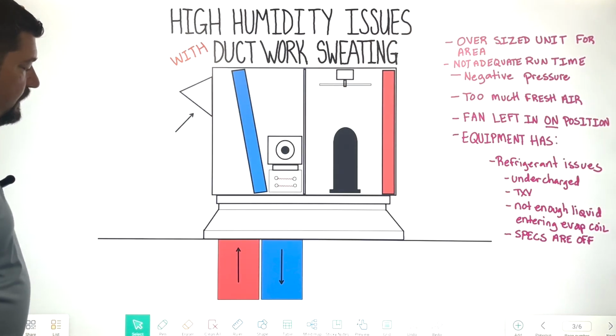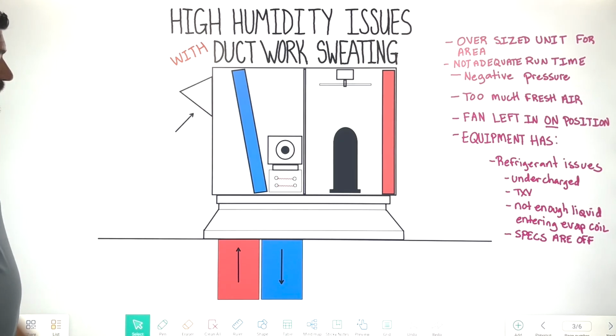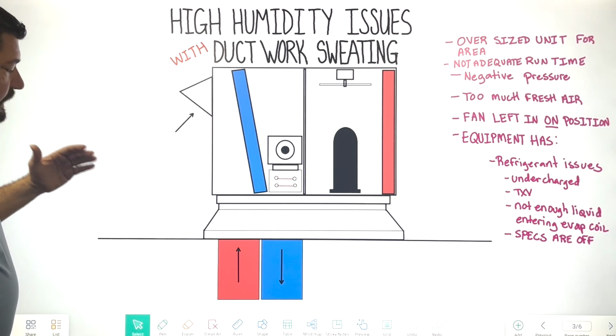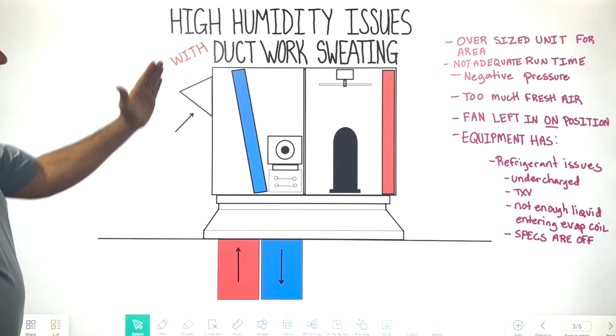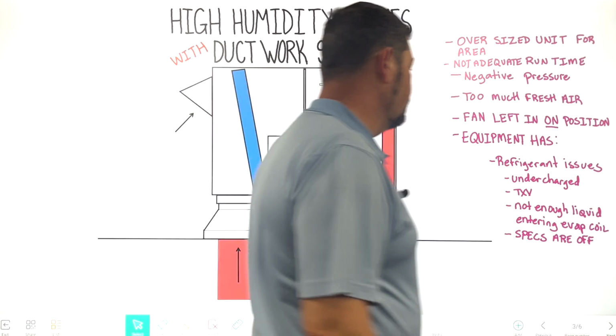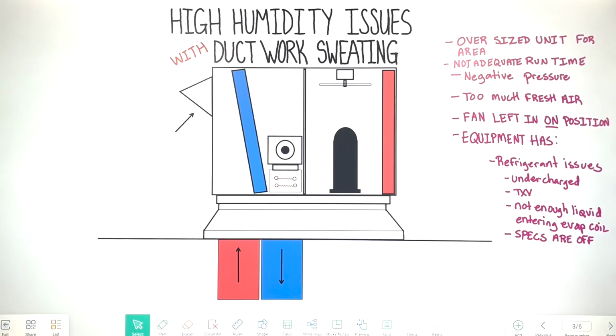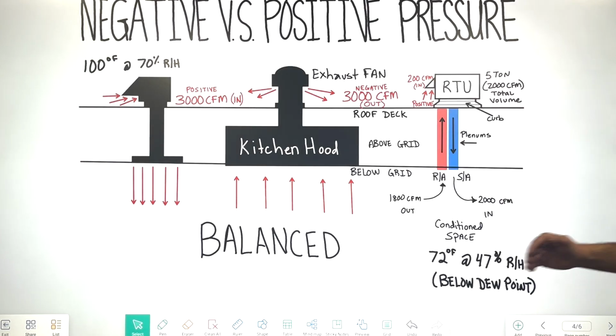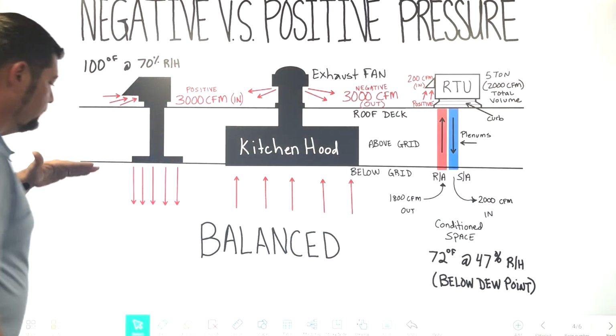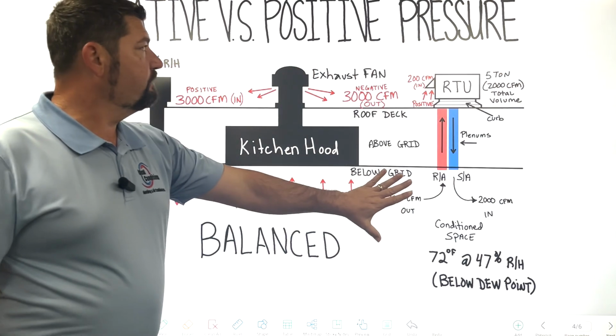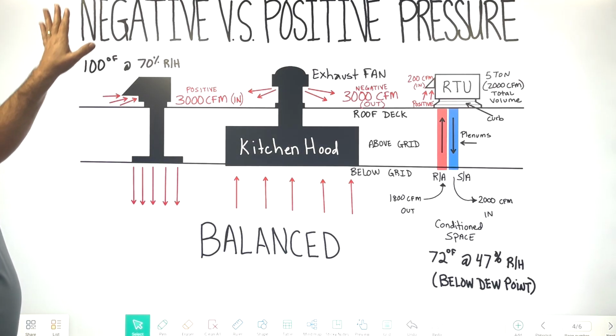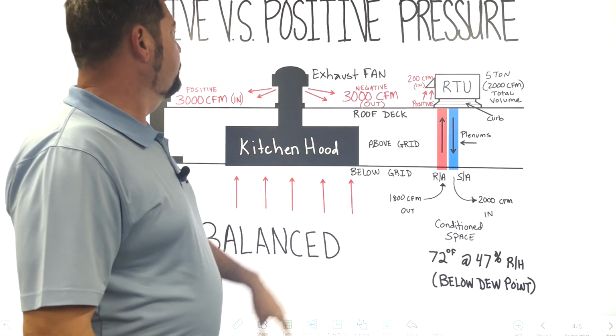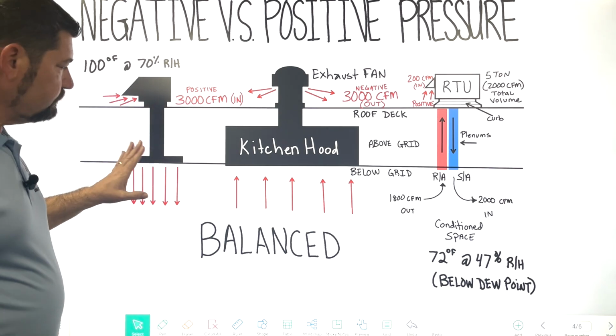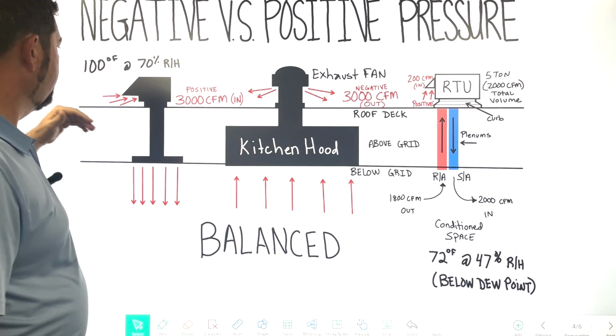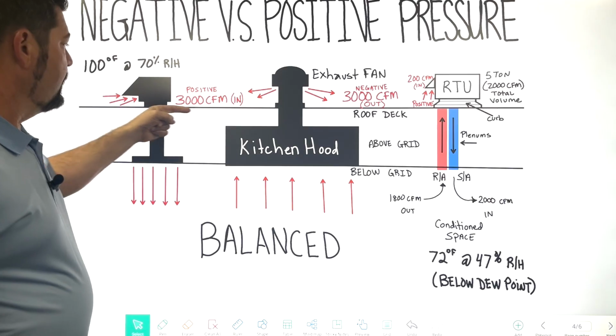So you got to think about it. You could have a lot of water standing here, a lot of sunlight adding more heat. There's more evaporation up here. Anything that can add more humidity back into the building is going to be a concern on some days versus others. But if we were to look at what I'm talking about below that ceiling grid in this diagram here, I just want to compare and educate you on negative pressure versus positive pressure. All right, so just to go over the illustration here, this top line is that roof deck again.